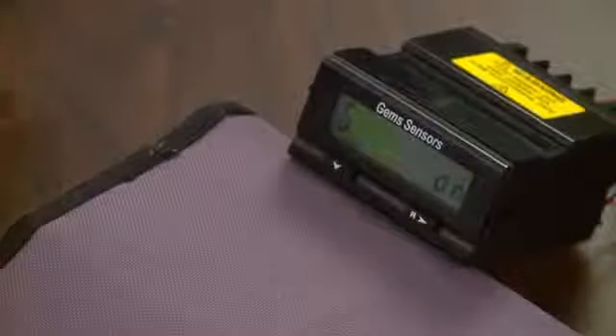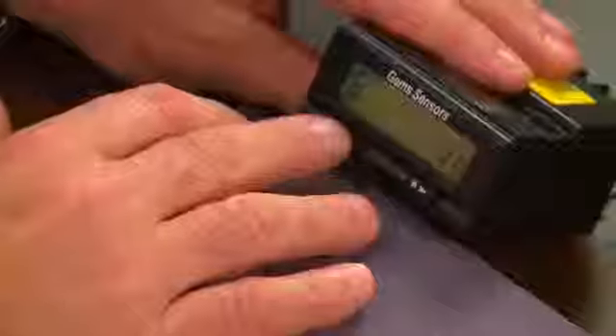Step 6 just says on or off. It'll give you a choice, and that's when you're in the total mode, whether you reset it or not. Meaning it just counts increments upwards in the total mode forever. But maybe at some point in time, just like your trip odometer on your car, you want to reset it to 0. So I'll leave it on, and that way when I press the R key, when it's in the run mode, it'll reset to 0. We are actually done now with programming the sensor.